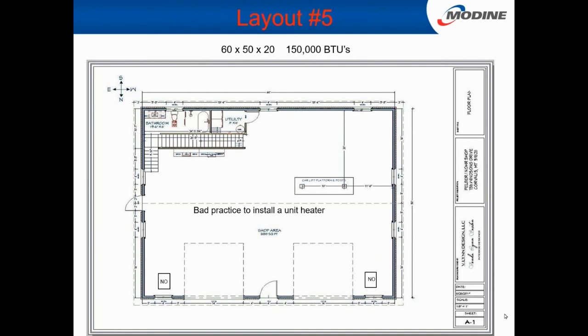In this case, back there by the sewer fittings, you got that unit heater right there by the garage. What is that? I don't know what it is. It's a terrible spot heater. It doesn't look like it runs. They open that door, it runs constantly. Yeah. There's no heat over there whatsoever. See, there would be a perfect application for an infrared. Right.